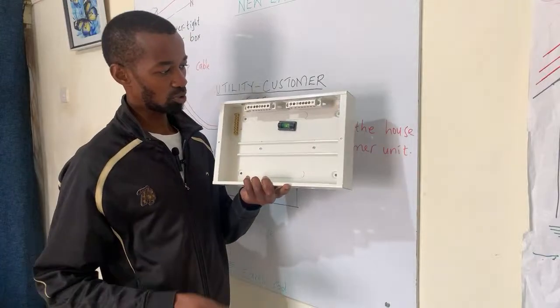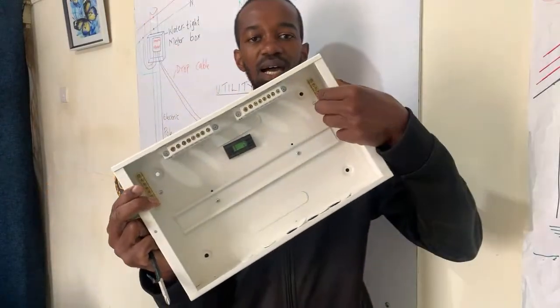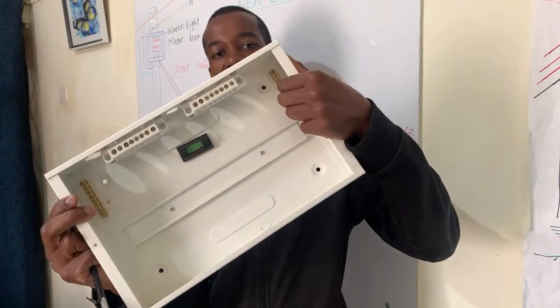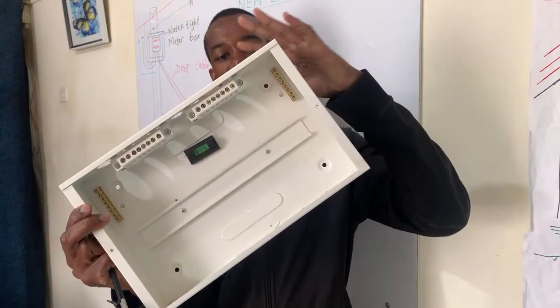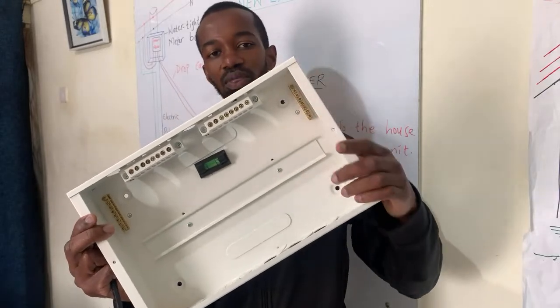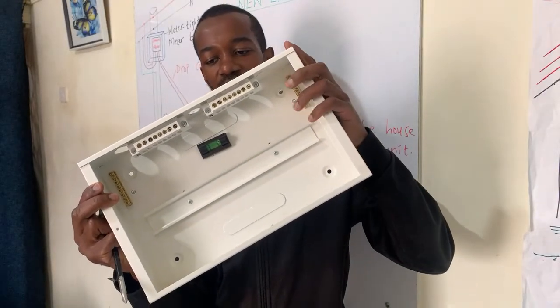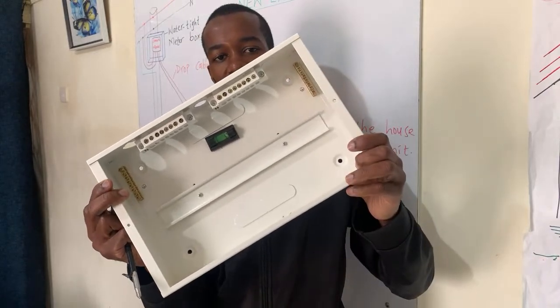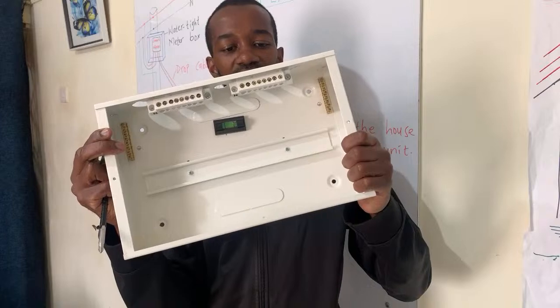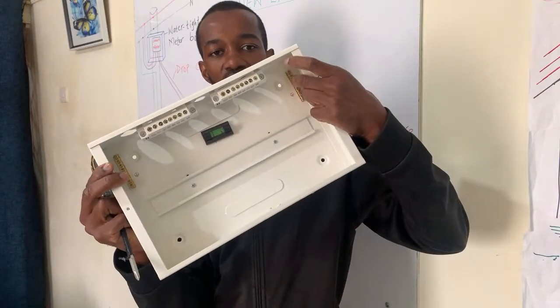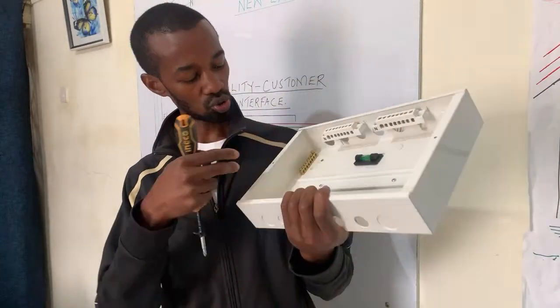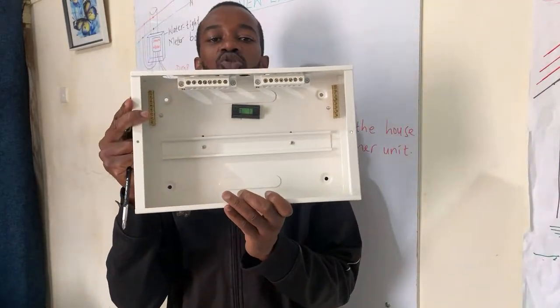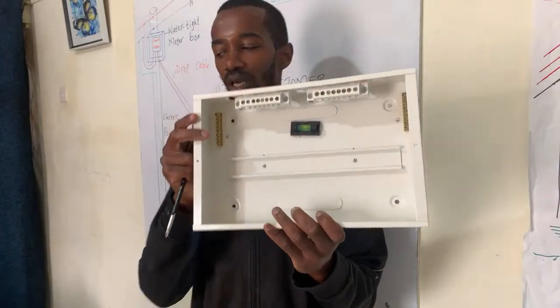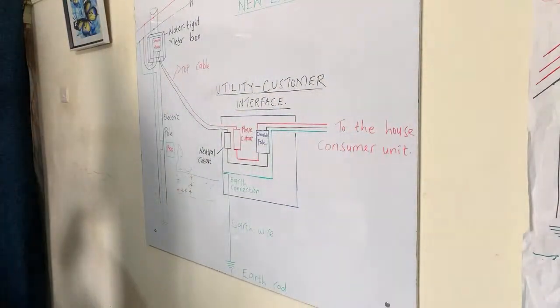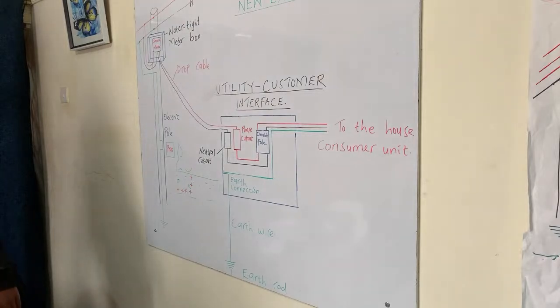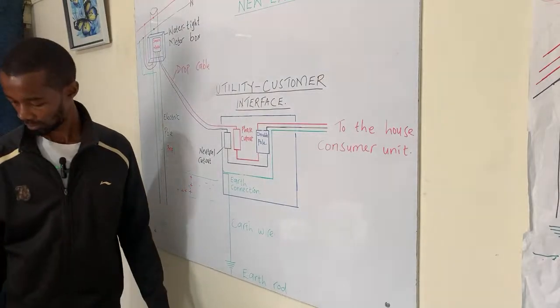So at this particular point, you will have that bar, which is the earth bar. It is also in contact with the metallic surface of this consumer unit. Remember, we said that any metallic part in the electrical system must be earthed. So the earthing connection is done at this point and also at this point. So my consumer unit has two earthing points, as you can see, to guarantee the user maximum protection when it comes to earthing. All right.